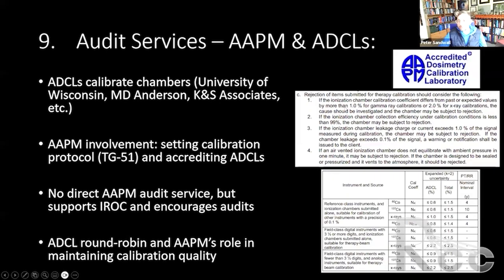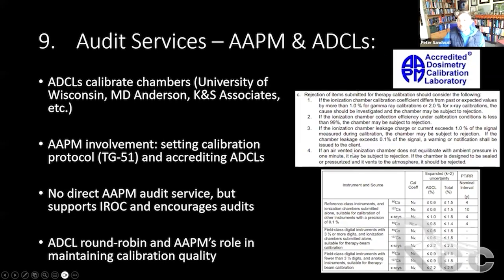If it has a calibration coefficient that differs by more than 1% for gamma or 2% for X-ray. This could be due to the flaking of the interior wall. There can be different reasons for this, but if your chamber calibration changes significantly, this is likely due to a change in the mechanical integrity of the chamber itself. It also talks about the collection efficiency, that it should be 99%. The ionization chamber leakage charge should not exceed 1%. And if an air vented chamber does not equilibrate with ambient pressure in a minute, it also may be subject to rejection.